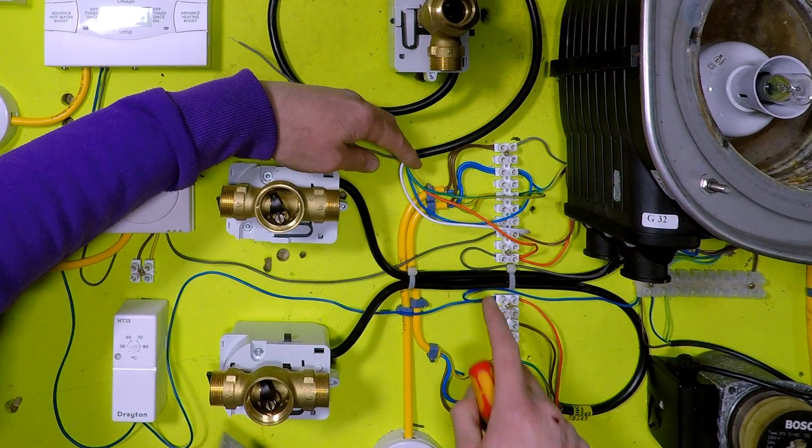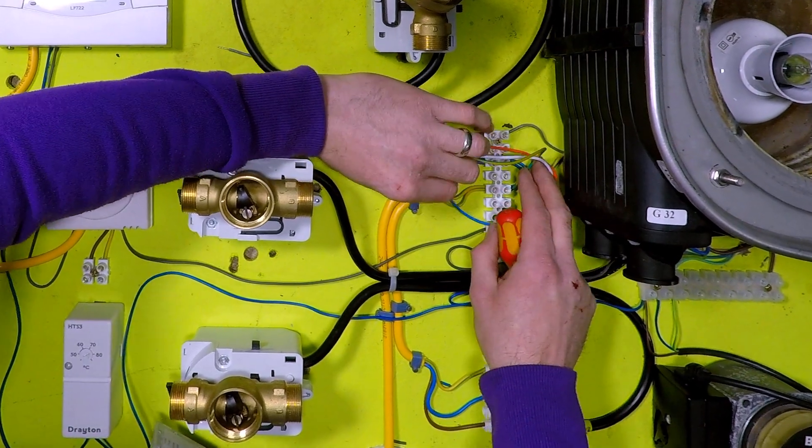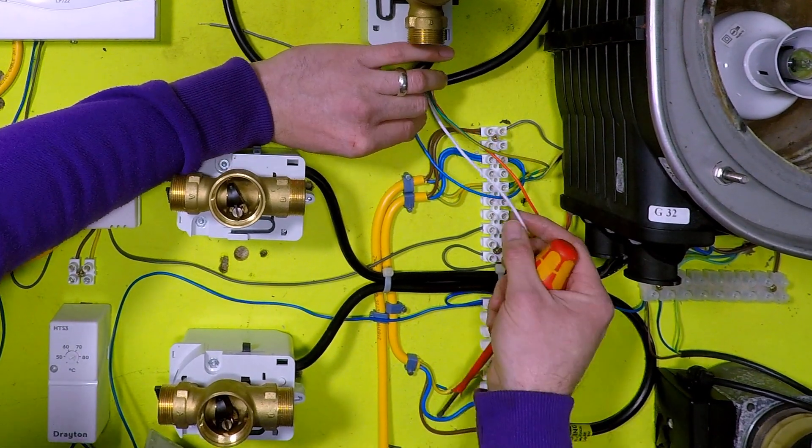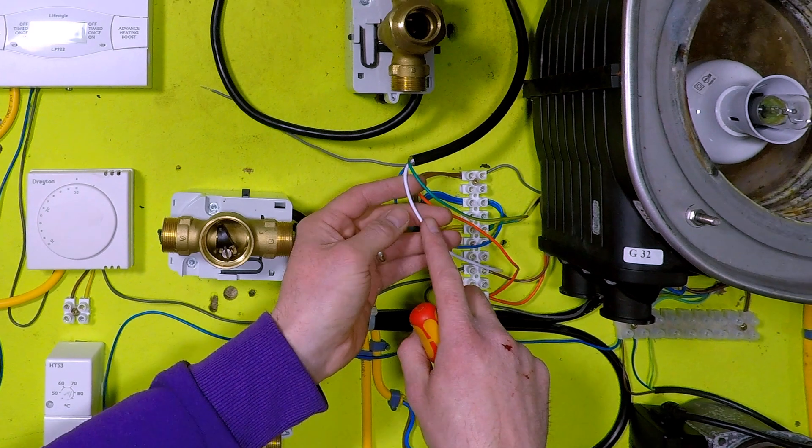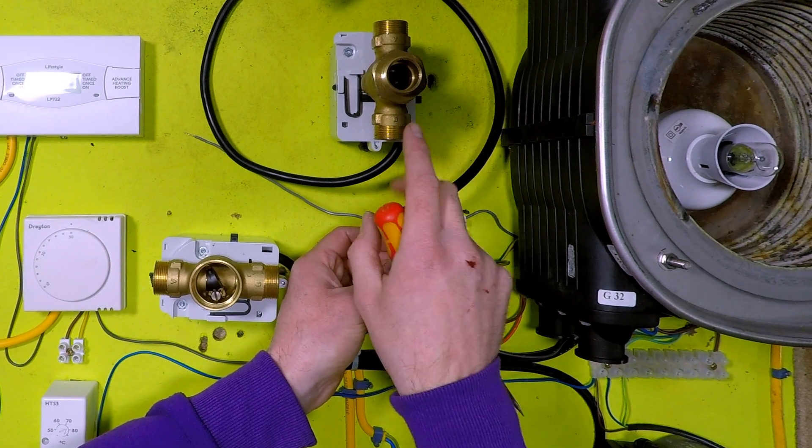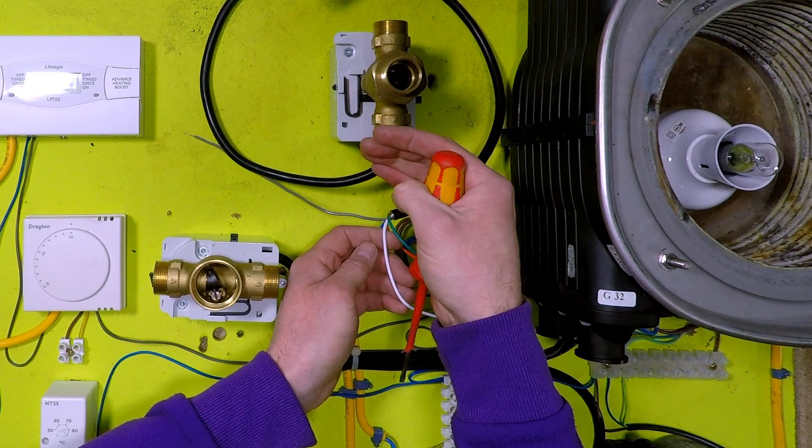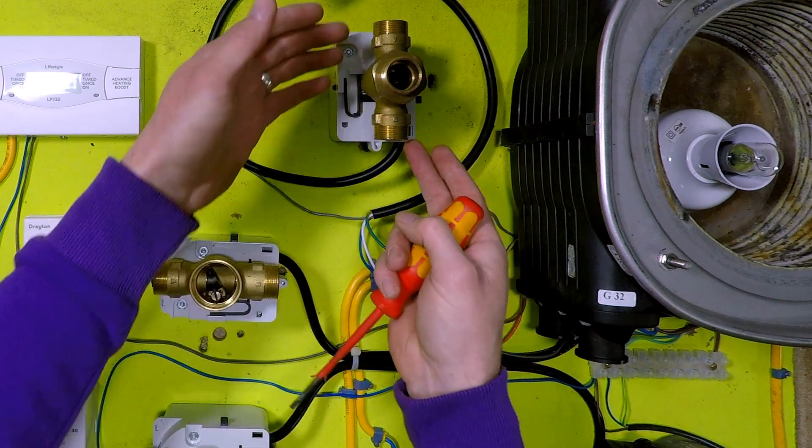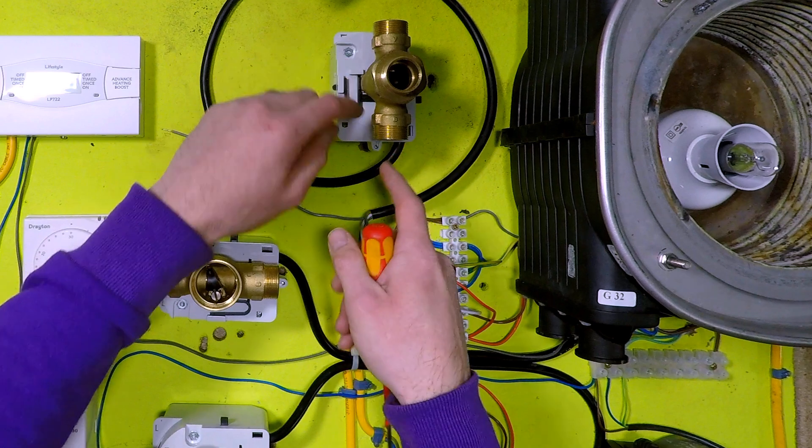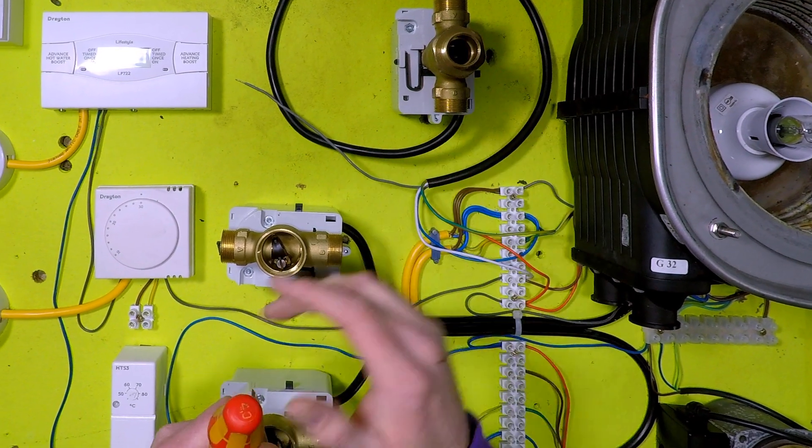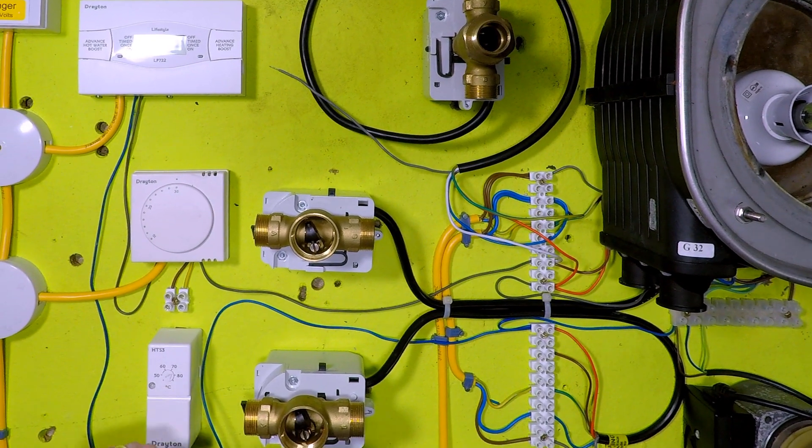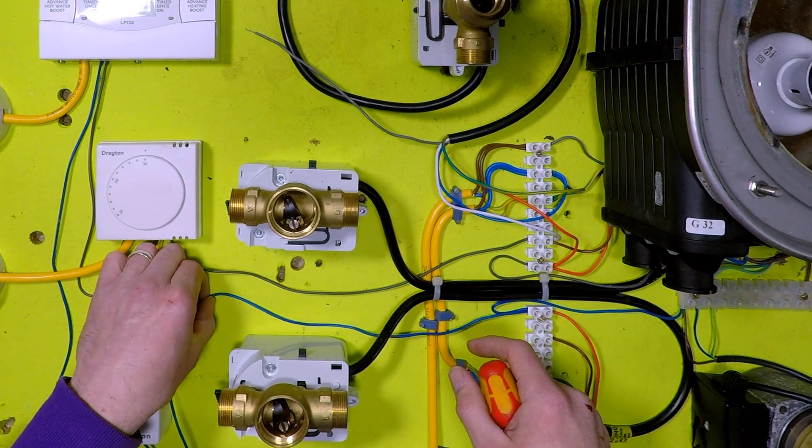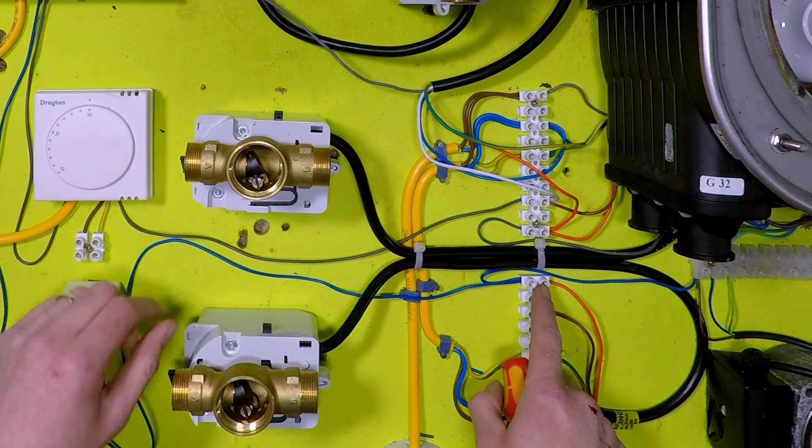From the room thermostat it comes in here. Let's move this to the white wire, and all this white wire will do in a three port is move the valve to mid position. And mid position, the waterways open to both ports, both heating and water. Okay, that's all that does.